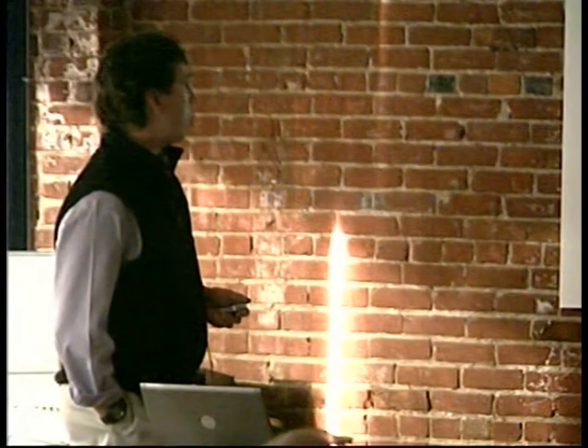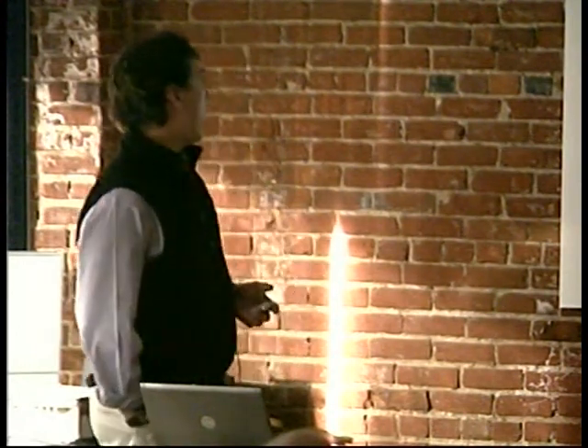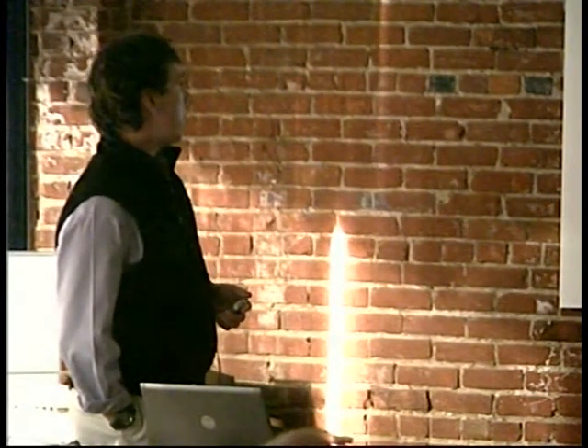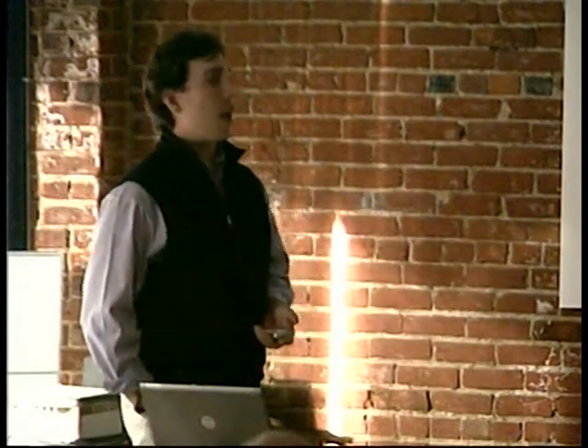The third goal here: utilize natural daylight as primary light source where available. Incorporate daylight harvesting techniques to reduce energy usage, and I'll get into that here briefly. Alongside of that is to minimize the personal interaction with daylighting controls. In other words, what I'm saying by that is utilizing technology that the users don't necessarily physically know that there's a change taking place. There's not a switch from the lights being all on to all off. It's gradual as the sun moves from one side of the building to the other. The lighting levels in that area will change linearly with the effects of the sunlight.